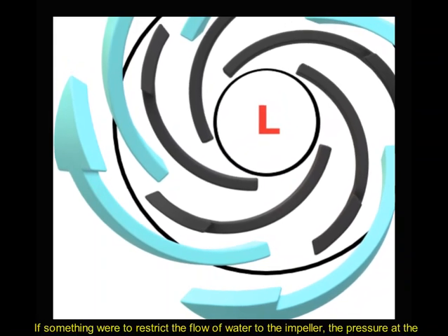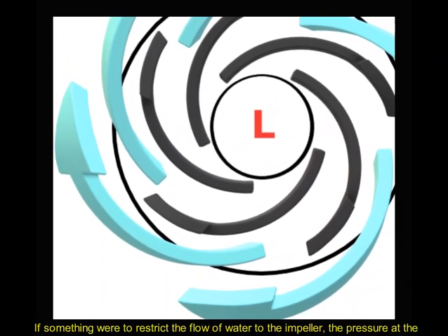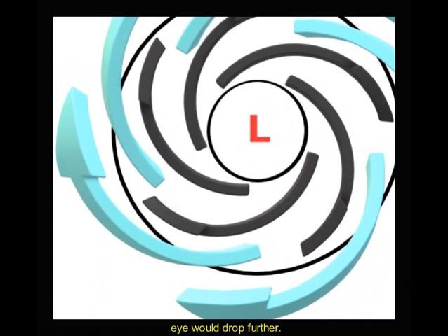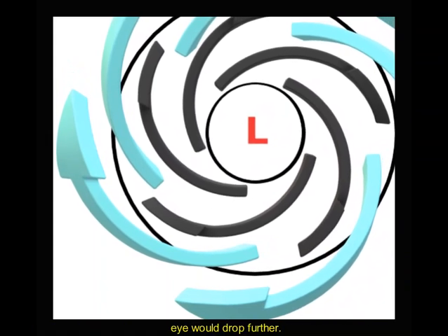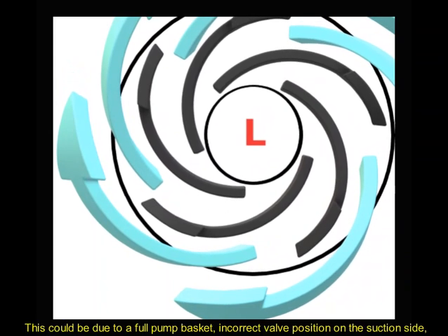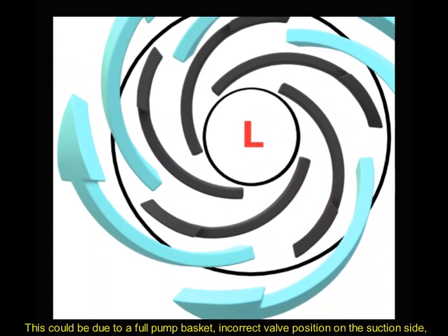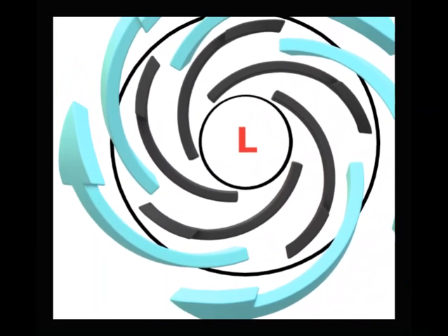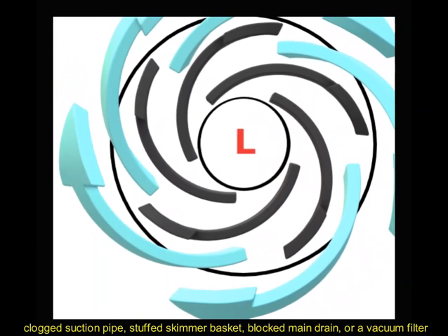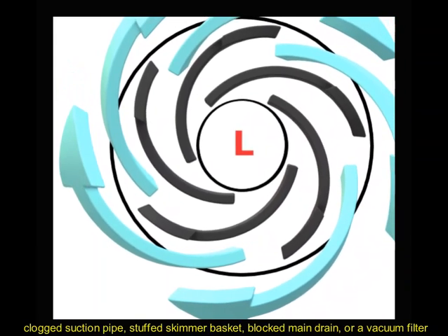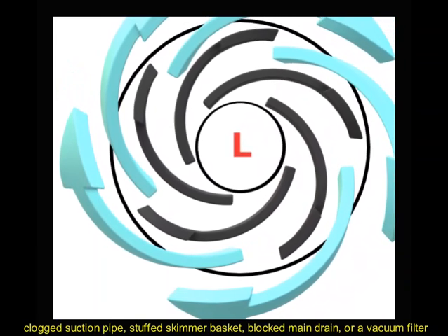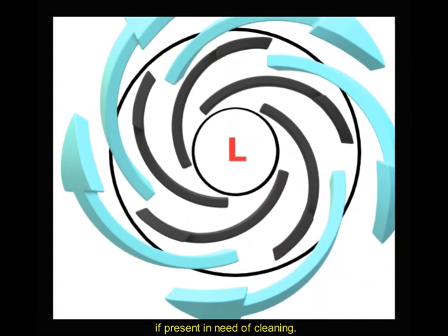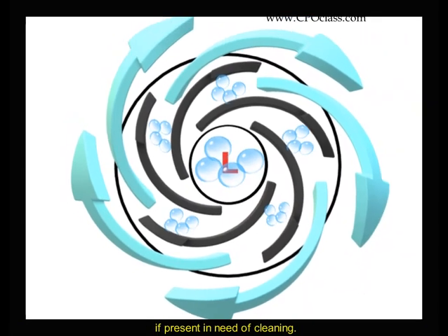If something were to restrict the flow of water to the impeller, the pressure at the eye would drop further. This could be due to a full pump basket, incorrect valve position on the suction side, clogged suction pipe, stuffed skimmer basket, blocked main drain, or a vacuum filter, if present, in need of cleaning.